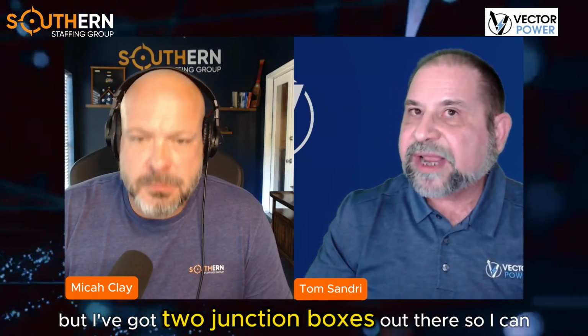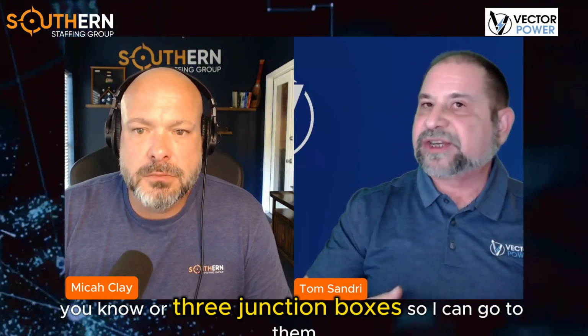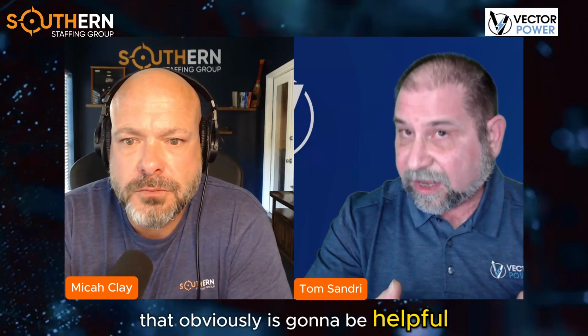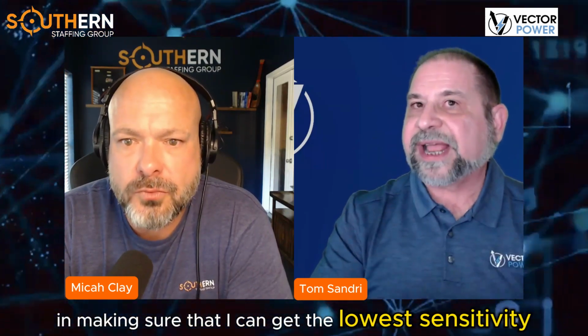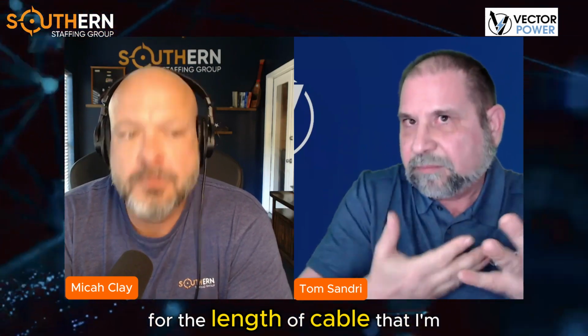If you've got junction boxes on the surface, I can no longer test the entire 7 miles, but if I've got 2 or 3 junction boxes out there, I can go to them, isolate the cable off the junction box, and break it down into smaller segments. That helps make sure I can get the lowest sensitivity for the length of cable I'm measuring.